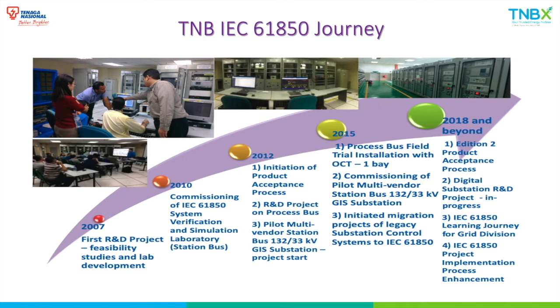In parallel, the transmission division of TNB started a multi-vendor station bus substation project. In 2015, we successfully completed a field trial installation of an optical current transformer for one bay, commissioned the multi-vendor substation project, and started migration projects for legacy substation control systems to IEC 61850.